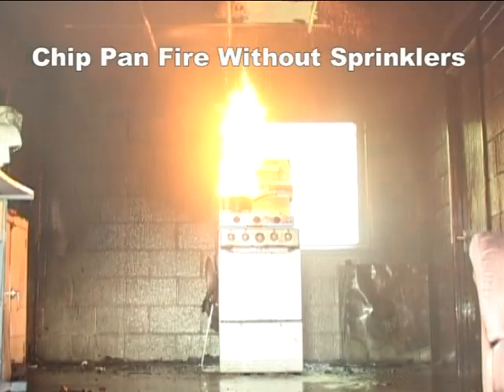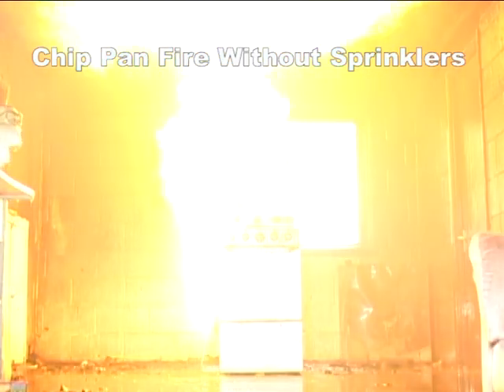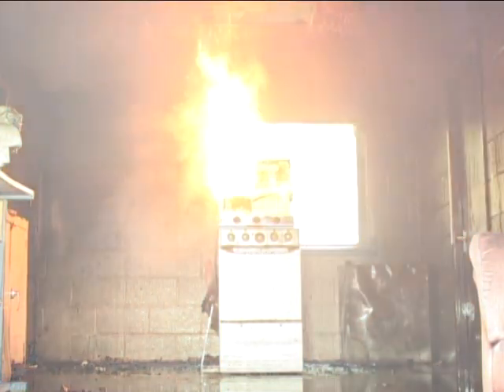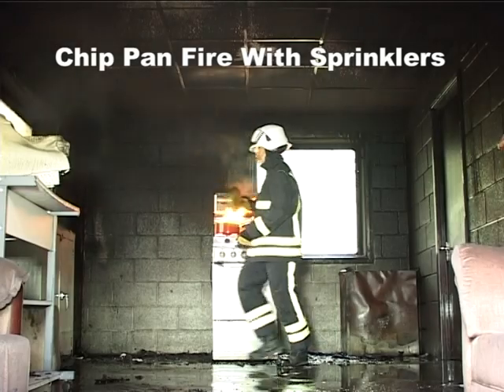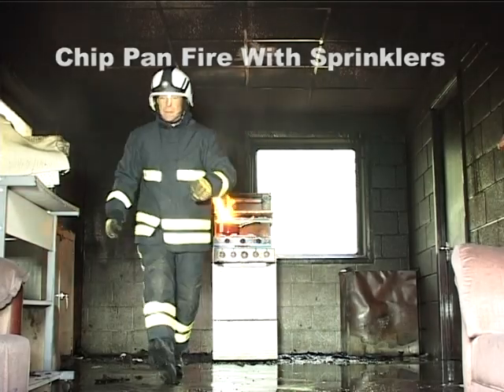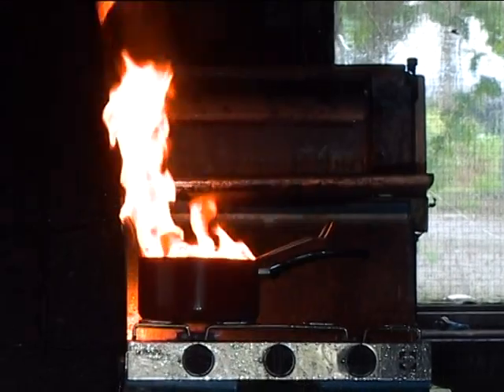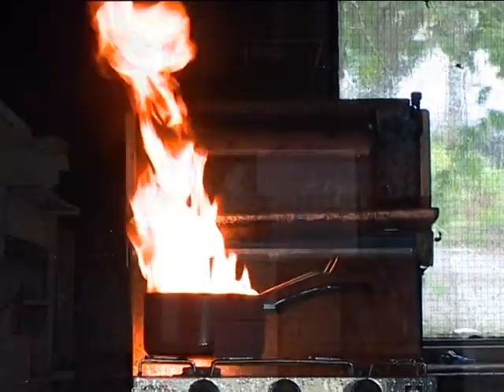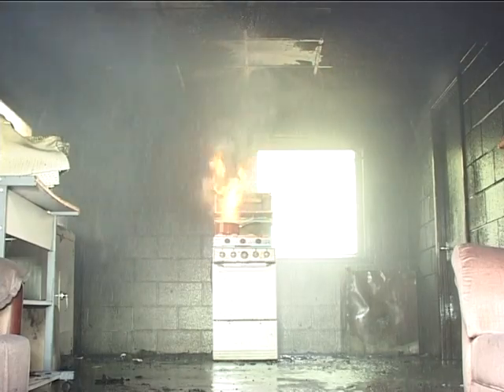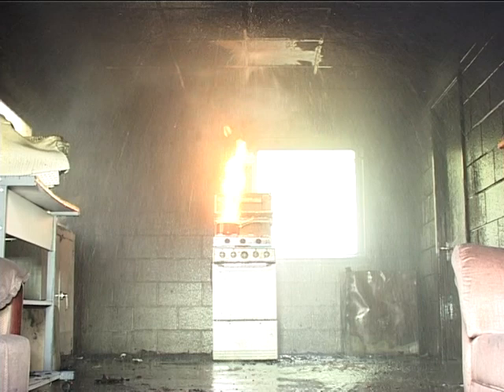This is what happens when you pour water onto a chip pan fire. A fireball engulfs the room. It's a common myth that the same thing will happen if a sprinkler system activates over a chip pan fire. Because the sprinkler system delivers small droplets of water, instead of creating a fireball, the burning oil is quickly cooled and the fire will be either controlled or extinguished.